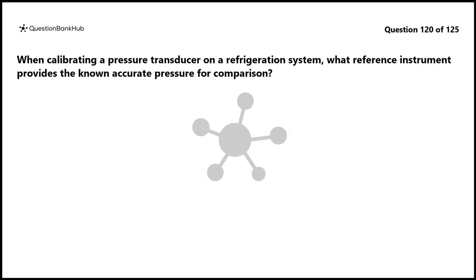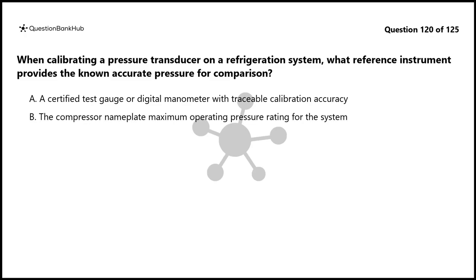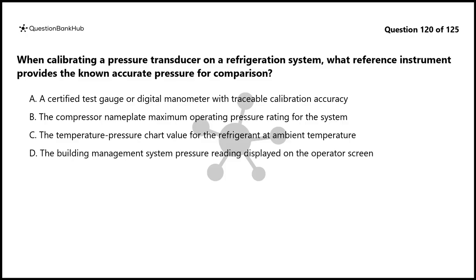Question 120. When calibrating a pressure transducer on a refrigeration system, what reference instrument provides the known accurate pressure for comparison? A. A certified test gauge or digital manometer with traceable calibration accuracy. B. The compressor nameplate maximum operating pressure rating for the system. C. The temperature pressure chart value for the refrigerant at ambient temperature. D. The building management system pressure reading displayed on the operator screen.